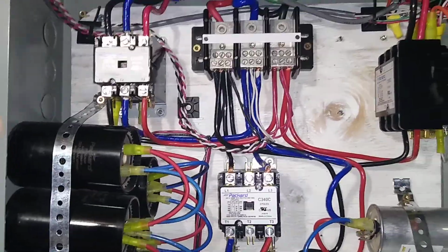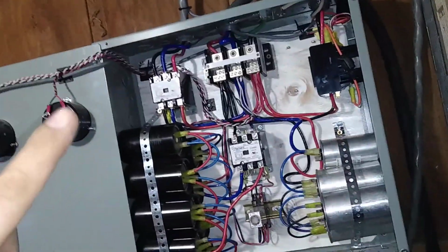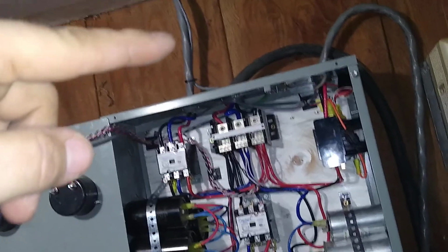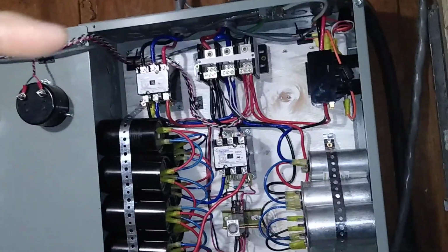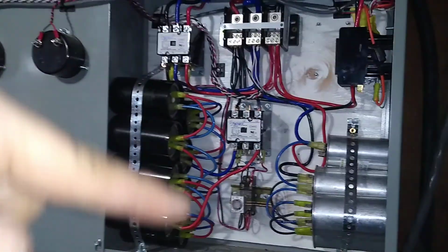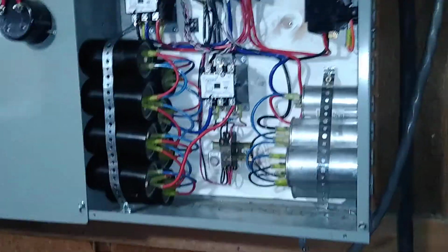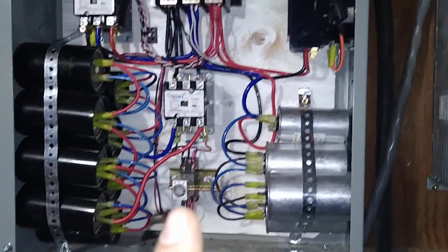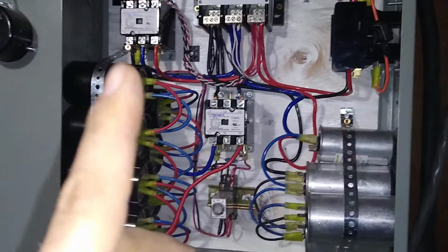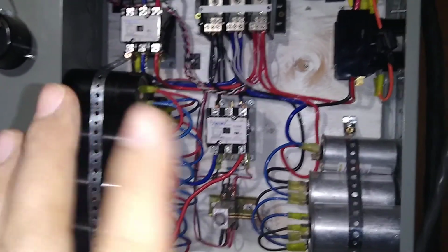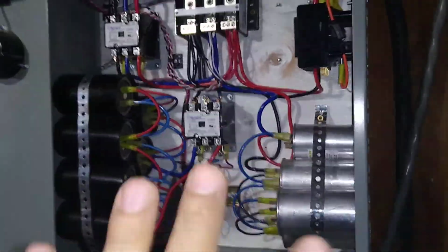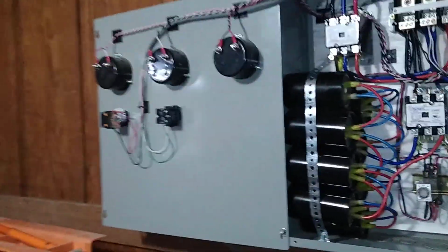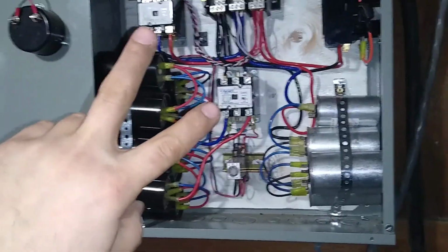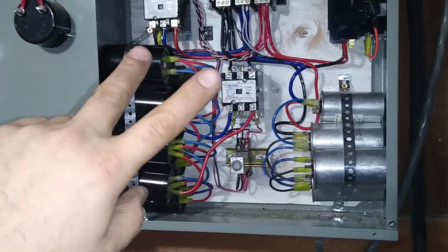So that when the air compressor is calling for power, let me shut this off. When the air compressor is calling for power via that little wire there, it will start this solely by itself. It'll get the pony motor up and running. Then once the start caps are pulled out, which only pull out when the motor's up to speed because it's timed, then the output contactor will turn on, which means now the unit is supplying full power, full voltage on all three legs. Then it'll start the air compressor. So it's only about a half a second, so this one pulls in instantly. As soon as that one lets go, this one pulls in and starts supplying power to the equipment.